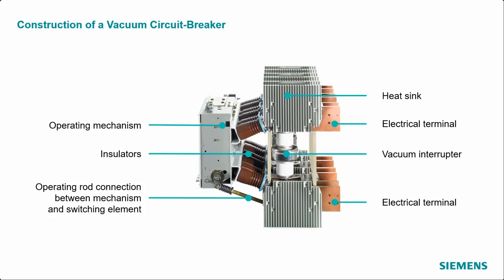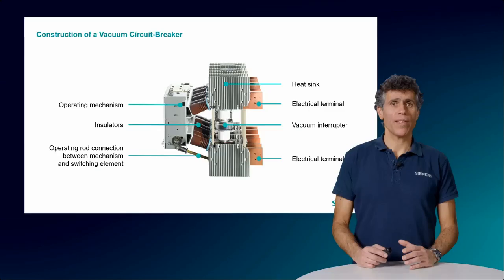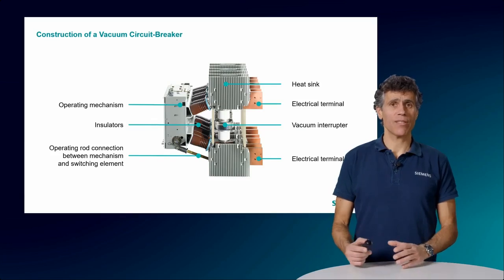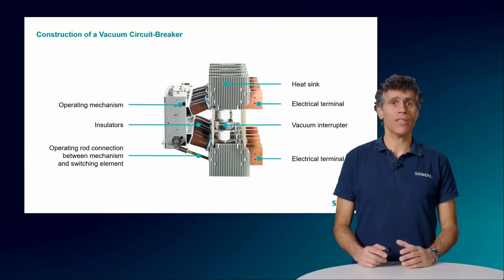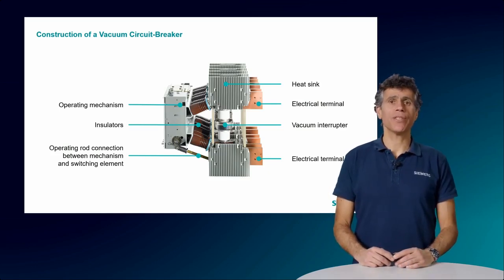The electrical terminals are the points where the circuit breaker connects to the electrical circuit. They need to be robust enough to handle high currents and ensure a low resistance connection. They must also be positioned in such a way that the connection to the switchgear can be done, which is not always an easy task because all switchgears are differently built.